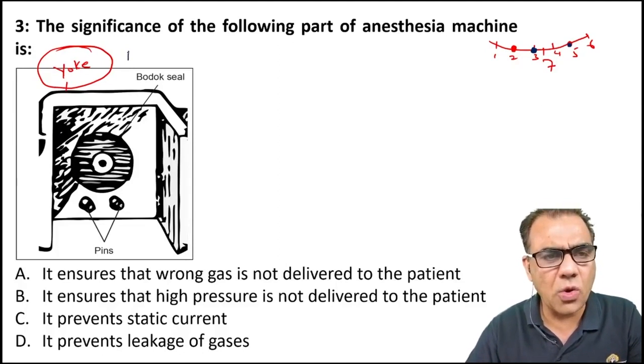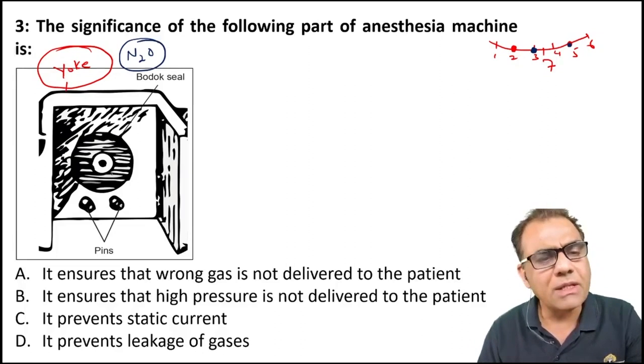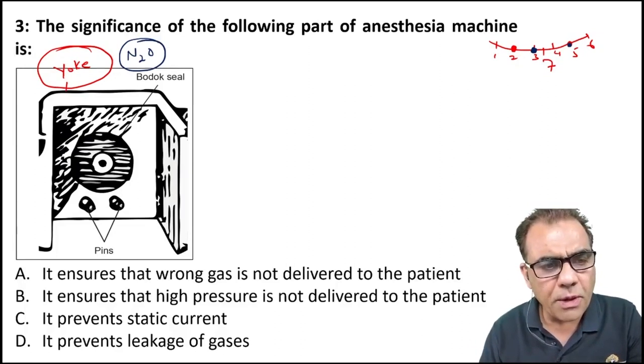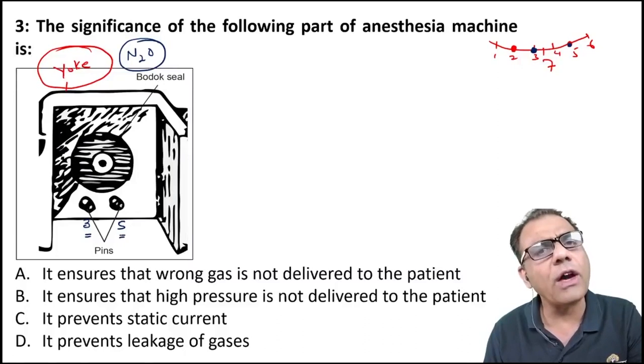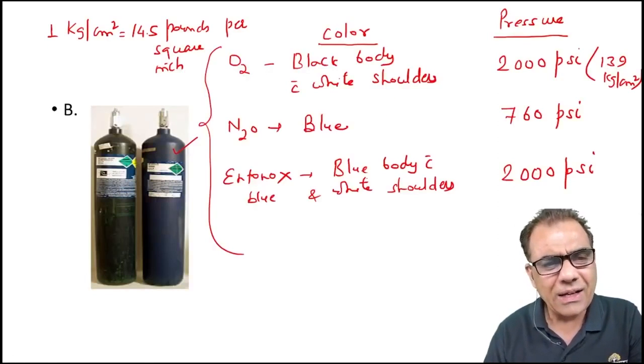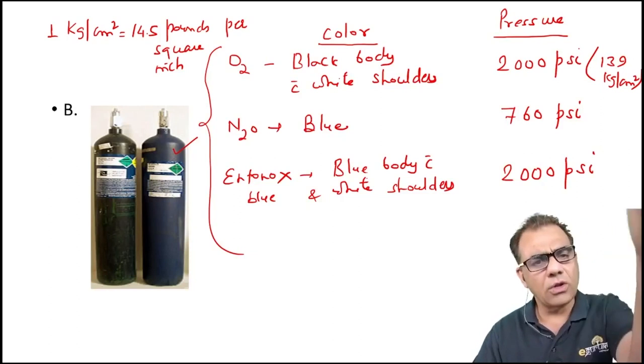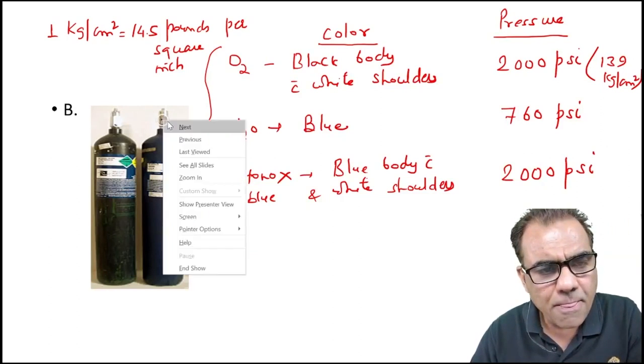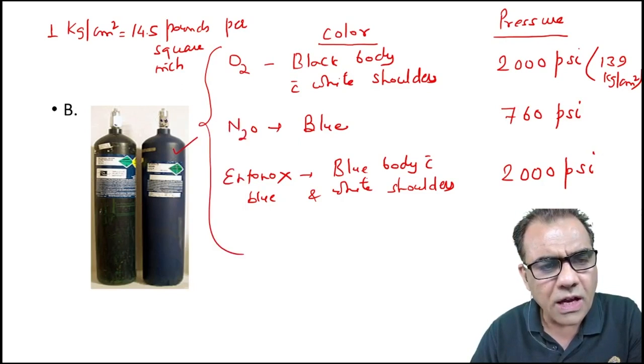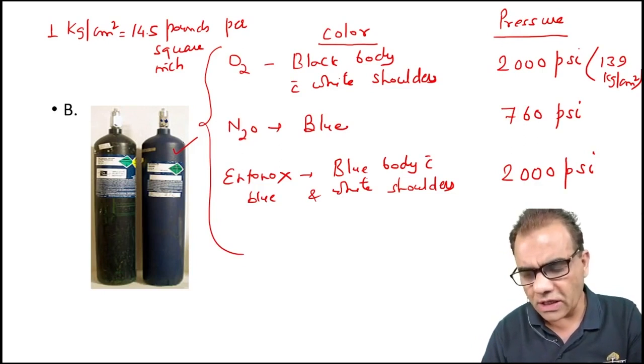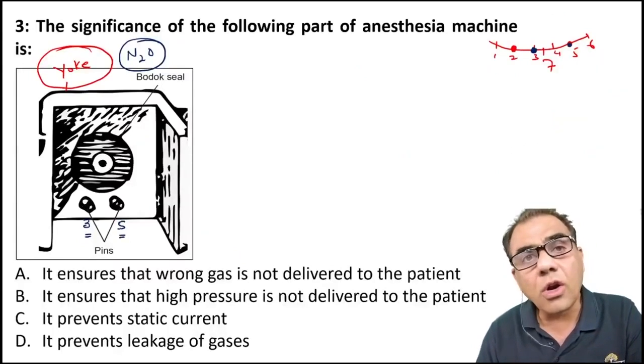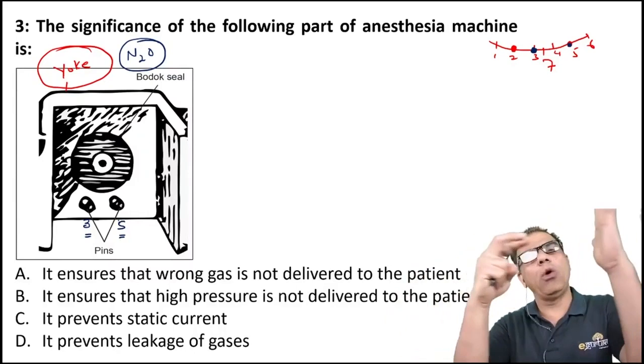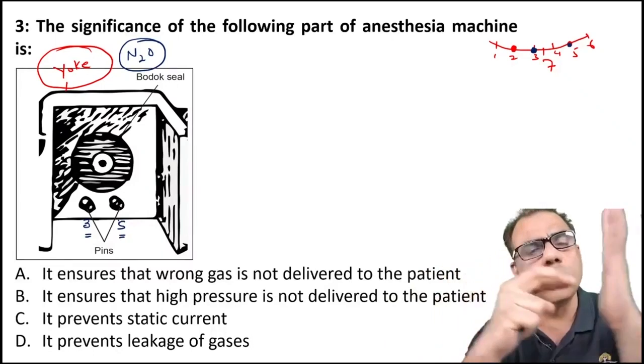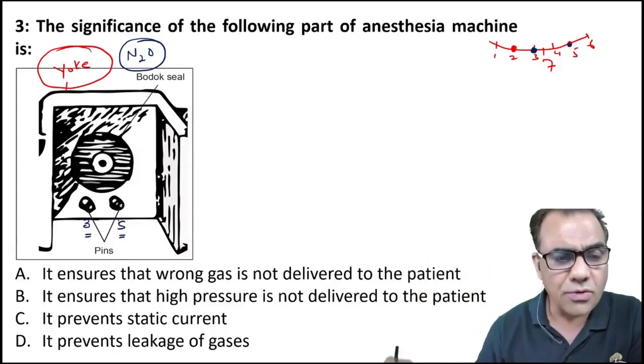Now say I consider this yoke as that of nitrous oxide. It means the nitrous oxide cylinder will be fitted here. So what will be the pin positions of these two pins? One will be positioned at 3 and the second will be positioned at 5. Now on the cylinder of nitrous oxide, on the other side, you will see that there are two holes which are positioned at 3 and 5. So only the nitrous oxide cylinder will be fitted here. You cannot fit an oxygen cylinder because the pins and holes on the cylinder will not match. If the pins and holes do not match, how will you fit the cylinder? So it's very important to prevent wrong fitting of cylinders.